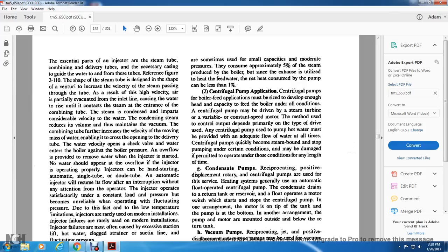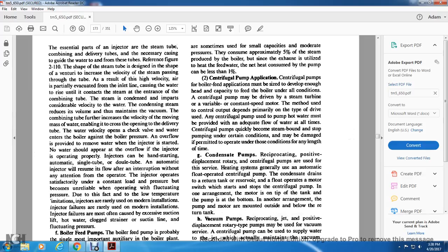The combining tube further increases the velocity of the moving mass of water, enabling it to cross another gap into the delivery tube. The water velocity opens the check valve and feeds water into the boiler against the boiler pressure. An overflow is provided to remove the water when the injector is started. No water should appear to overflow. The injector is then operating properly.